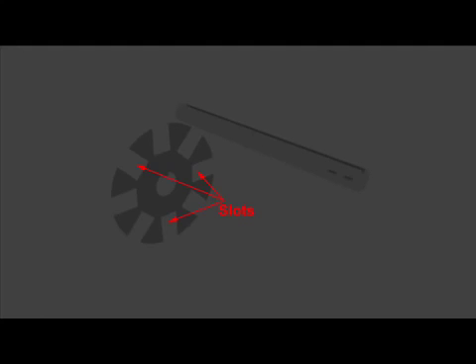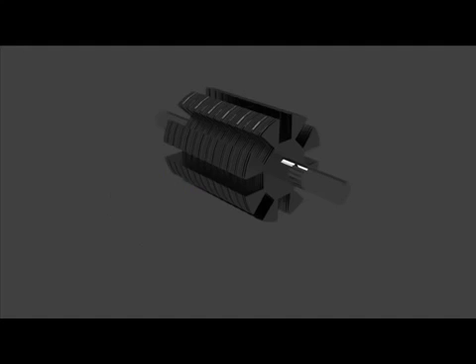The slots are either die cut or punched on the outer periphery of the circular core. Stamping or the keyway is located on the inner diameter. The slots are normally open type and usually placed parallel to the axis of the armature but are also sometimes skewed at a small angle to avoid vibration of teeth.